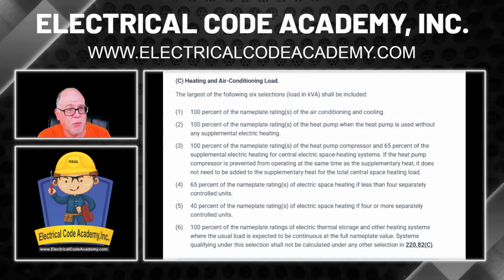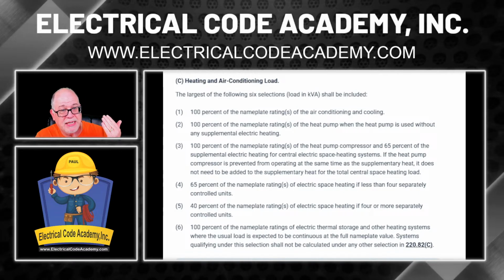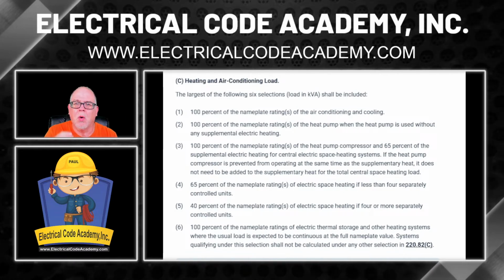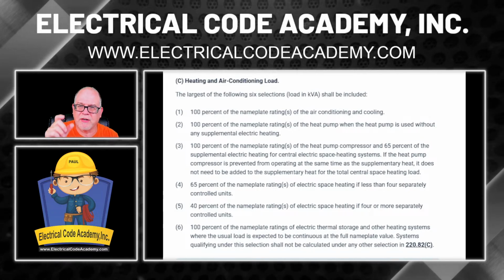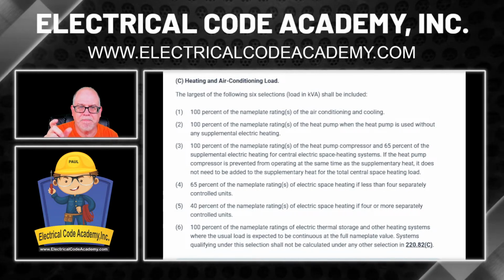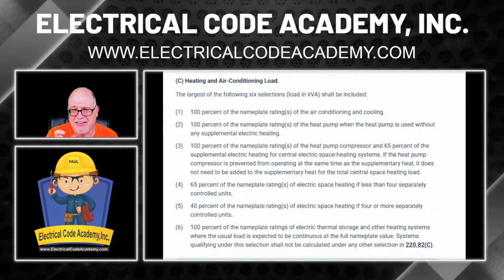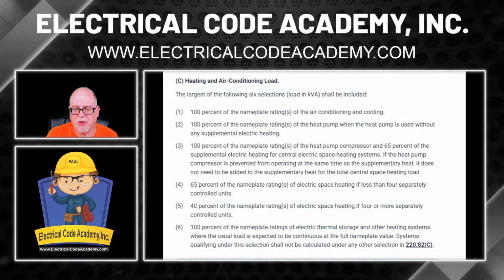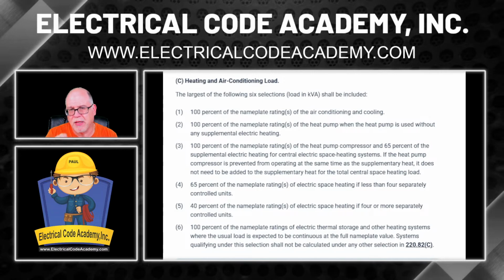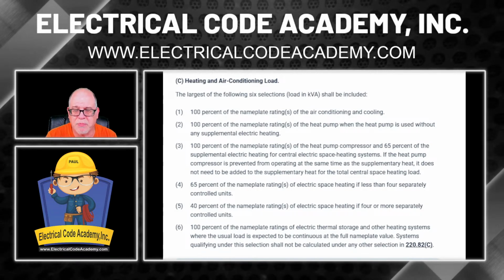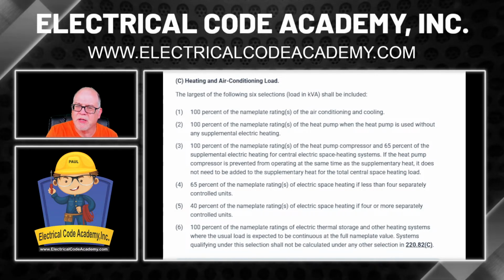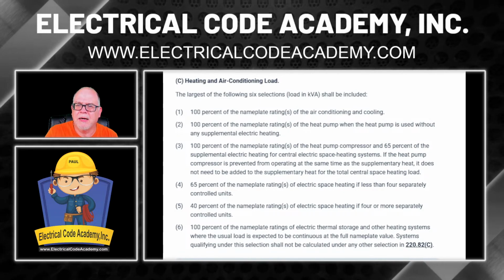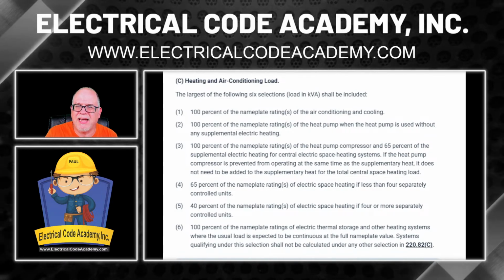And we know our heat. There were 6 of them at 3 kW each. So when it comes to the AC, we're going to take the full value at 100%. Now we need to see that heat. Looking down the list, number 2 is a heat pump. Number 3 is still talking about heat pumps. Number 4 is 65%, but that's electric space heating when you have less than 4.